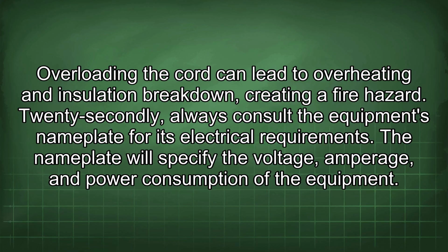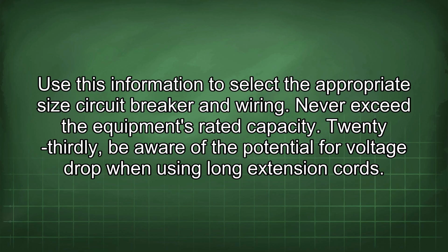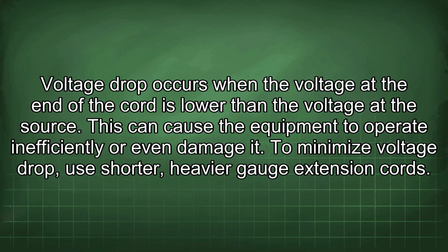22ndly, always consult the equipment's nameplate for its electrical requirements. The nameplate will specify the voltage, amperage, and power consumption of the equipment. Use this information to select the appropriate size circuit breaker and wiring. Never exceed the equipment's rated capacity. 23rdly, be aware of the potential for voltage drop when using long extension cords. Voltage drop occurs when the voltage at the end of the cord is lower than the voltage at the source.